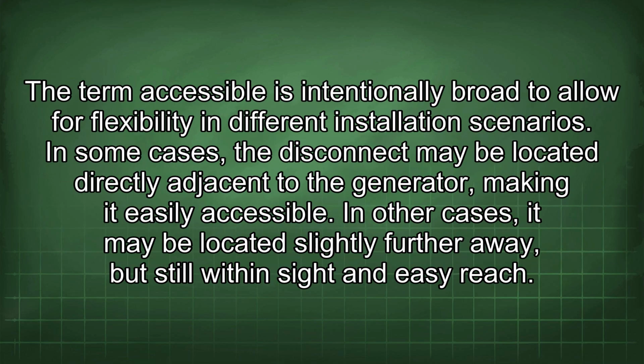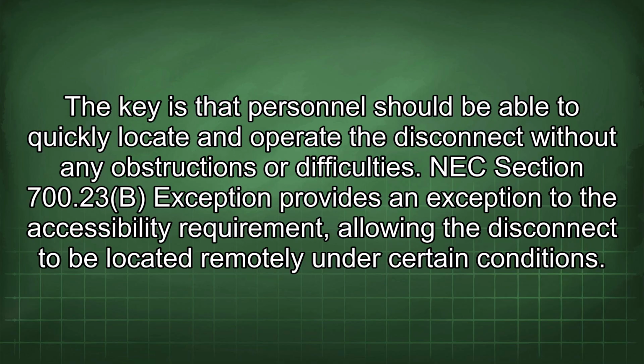The term accessible is intentionally broad to allow for flexibility in different installation scenarios. In some cases, the disconnect may be located directly adjacent to the generator, making it easily accessible. In other cases, it may be located slightly further away, but still within sight and easy reach. The key is that personnel should be able to quickly locate and operate the disconnect without any obstructions or difficulties.